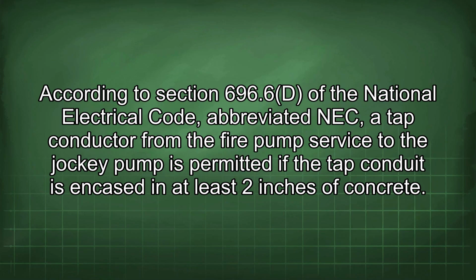According to section 696.6(D) of the National Electrical Code, abbreviated NEC, a tap conductor from the fire pump service to the jockey pump is permitted if the tap conduit is encased in at least 2 inches of concrete.